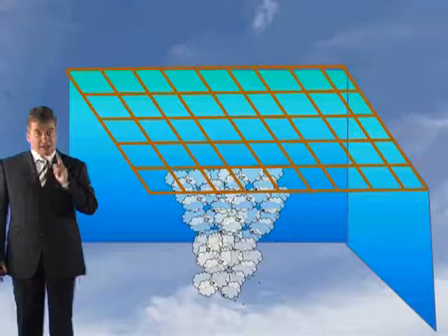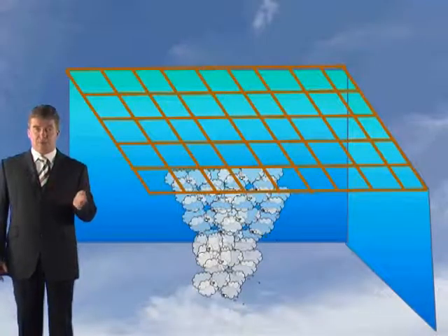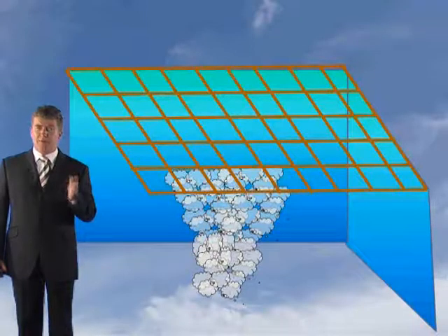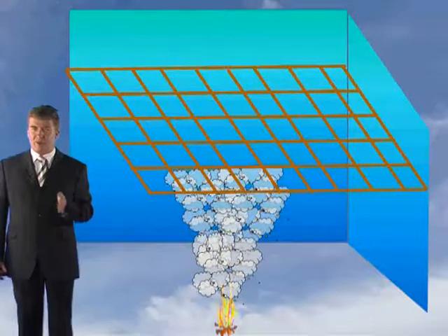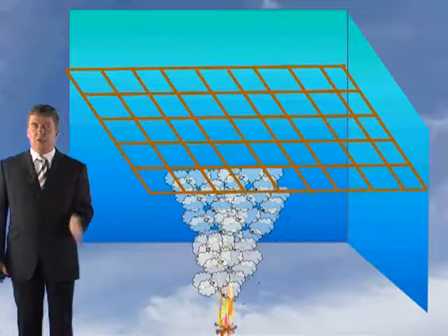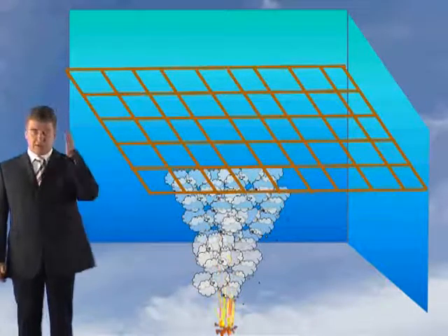Now, however, if the false ceiling is porous to smoke, in other words, it has an appreciable free area, any smoke screens forming the smoke reservoir must be continued above that ceiling. Now, if the proportion of free area is large enough, the reservoir and its screens may be totally above the false ceiling. Because what it's saying is, if it's got an appreciable amount of air, the smoke will just go straight through it. It will not have a massive impact on it. But you've got to work it out.